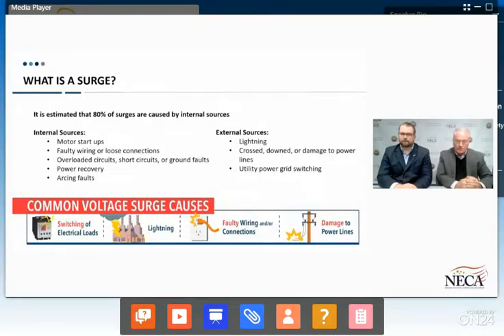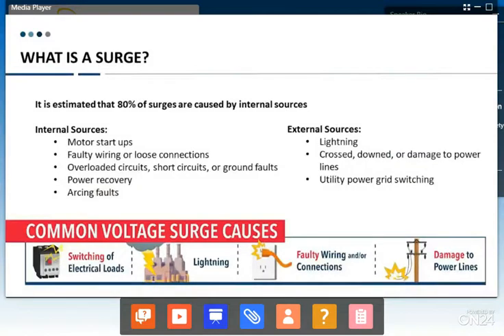To sum it up simply, switching operations on the utility side, and switching of loads within a facility, can cause inrush currents and result in surge events within the facility, even downstream from the service equipment. The majority of the sources folks are concerned with are internal to the facility, although external sources are very common, and of course lightning and other natural sources are always present.